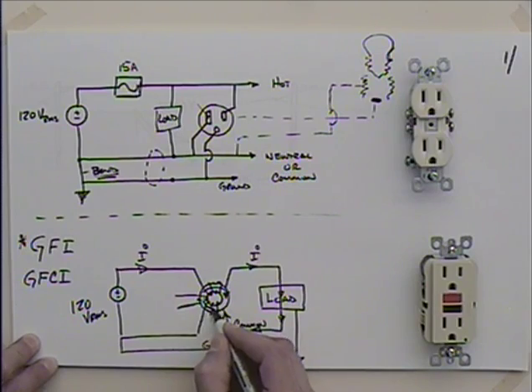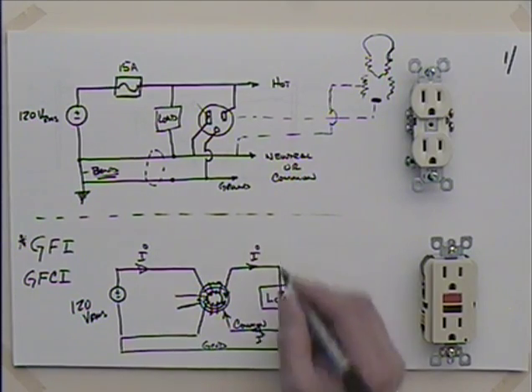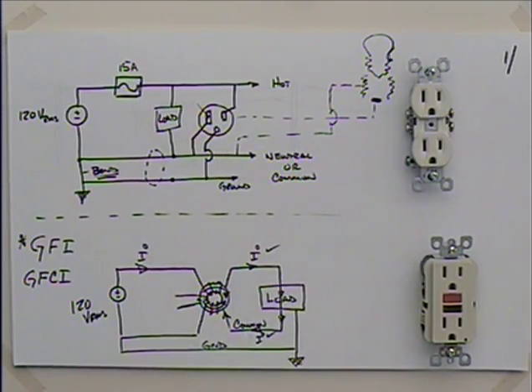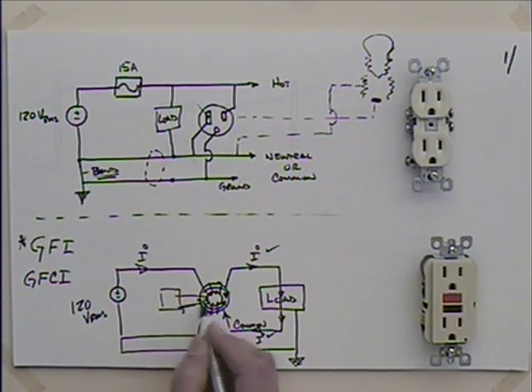The current comes out of here, the same current, goes through the load, and hopefully everything is okay in this load. The current will continue through here to the common, back through this. They wind this very carefully so that this produces a magnetic flux in the opposite direction. If this current here is the same as that current there, what do you know about those magnetic fluxes? They should be equal and opposite and cancel each other out.